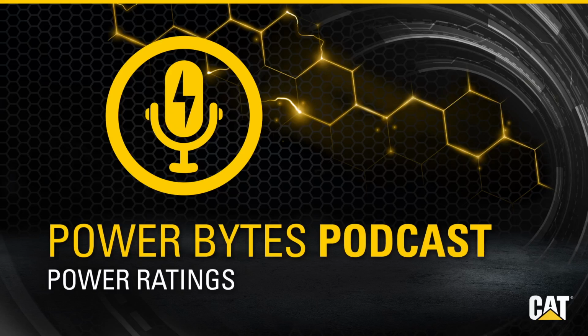The next rating category is the prime power, or PRP in the standard. These are a little bit different in that they allow for a variable load. Typically, they consider a 70% load factor, which means that over the course of a day, you may have some variations. During the day when everybody's up and working, you've got quite a bit of power usage, but maybe at night, the power rolls back. So over the course of a day, or even over the season, you'll end up with around a 70% load factor operating on the unit.